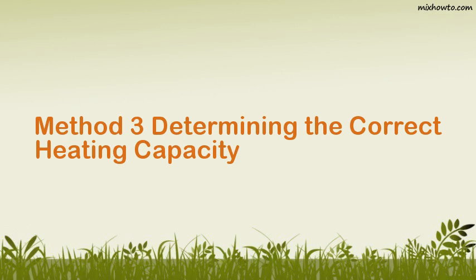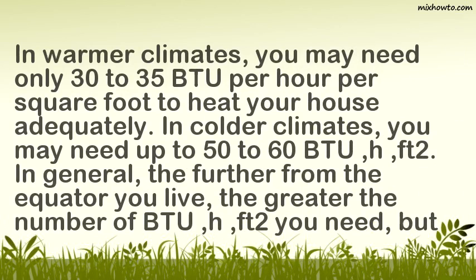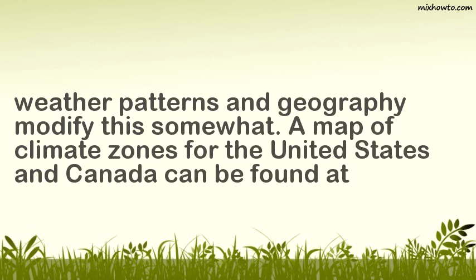Method 3: Determining the Correct Heating Capacity. Consider your climate. In warmer climates, you may need only 30 to 35 BTUs per hour per square foot to heat your house adequately. In colder climates, you may need up to 50 to 60 BTU/H/ft². In general, the further from the equator you live, the greater the number of BTU/H/ft² you need, but weather patterns and geography modify this somewhat. A map of climate zones for the United States and Canada can be found online.